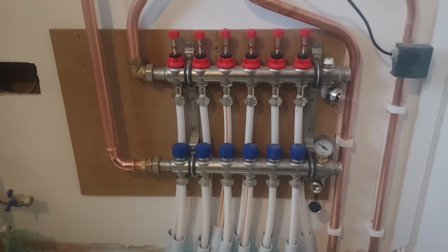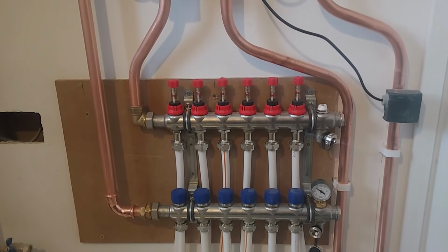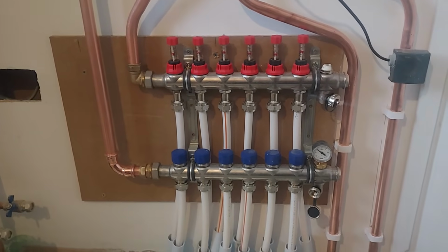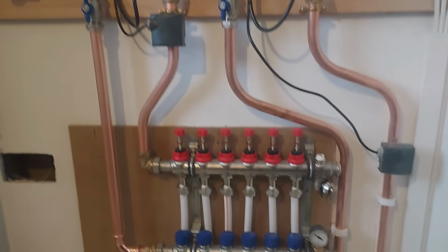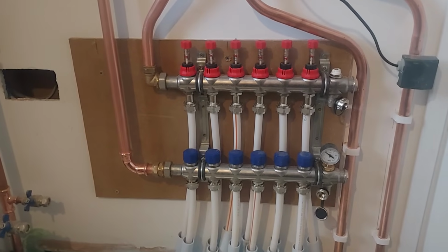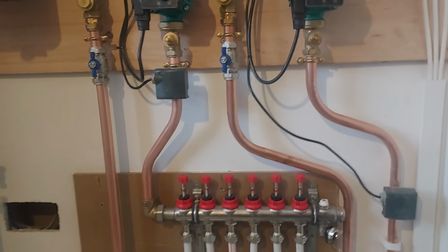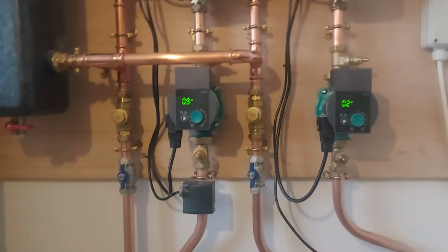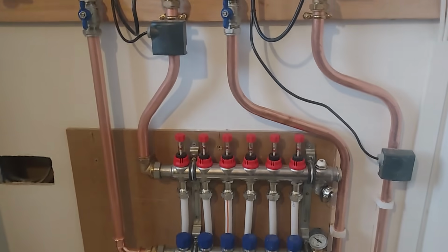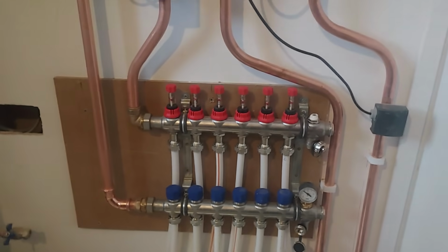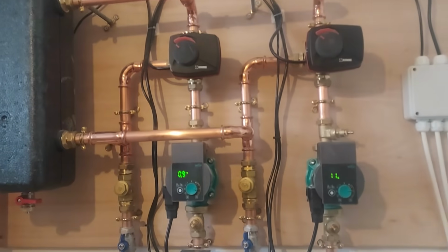So we've got a set of flow rates to set on these that will allow us to have different delta T's in each room to compensate for the static positioning between the pipes. So where we've got 150 mil spacings between the pipework, what we can do is increase or decrease the flow slightly to change the average surface floor temperature to correct the slight inaccuracies in floor output. And this is all designed to avoid the use of room stats. So we should be able to match very accurately the output of any floor without using any actuators and room stats. So we can make some fine adjustments on this.